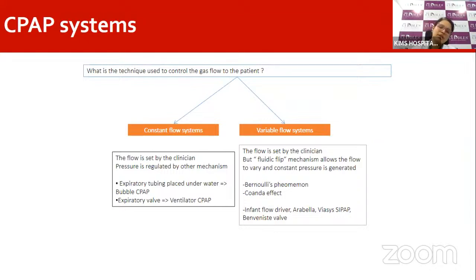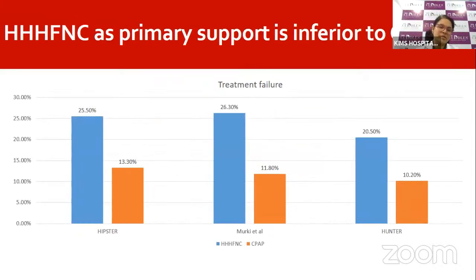There are 2 types of CPAP devices: constant flow systems, where the flow is set by the physician and pressure is regulated by either an underwater seal, like in bubble CPAP, or with an expiratory valve, like in ventilator CPAP. There can, on the other hand, be variable flow systems, wherein flow is set by the clinician, and a fluidic flip mechanism allows the flow to vary between inspiration and expiration. And constant pressure is generated during both inspiration and expiration. Some people believe this reduces work of breathing, but this has not really translated into clinical benefits.